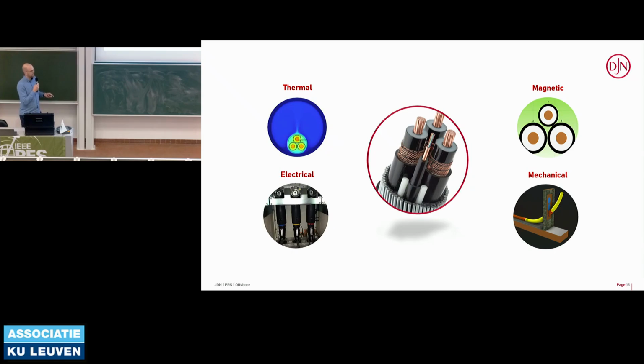For a submarine cable, there are several interfaces. You have a thermal impact, which depends on burial assessments or neighboring cables. You have the electrical scope, of course, which is to size the cable. Then you have the magnetic impact, as I explained before. Putting the plus and minus together is essential from an environmental point of view, to avoid magnetic impact issues. And we have the mechanical issue as well.